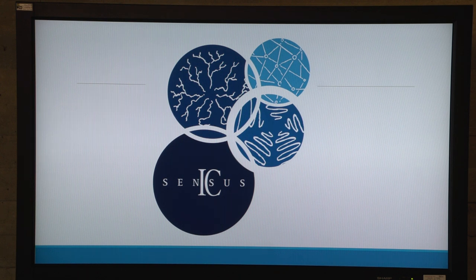The magnetic microparticles are a key factor in the speed of the device. The rate of diffusion of the sample through the layers was a limiting factor, but the magnetic attraction between the rare earth magnet and streptavidin magnetic microparticles increases the rate of diffusion and thus the delivery of results.